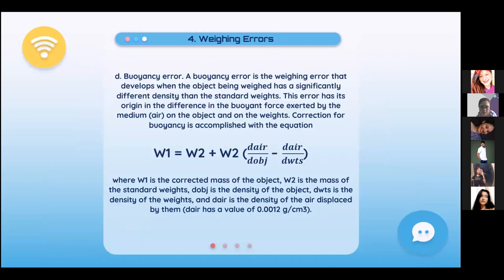Buoyancy error is the weighing error that develops when the object being weighed has a significantly different density than the standard weights, originating from the difference in buoyant force exerted by air on the object and on the weights. Correction for buoyancy uses the equation: W1 = W2 + W2 × (D_air / D_obj − D_air / D_wts), where W1 is the corrected mass, W2 is the mass indicated by standard weights, D_obj is the density of the object, D_wts is the density of the weights, and D_air is the density of air (0.0012 g/cm³).